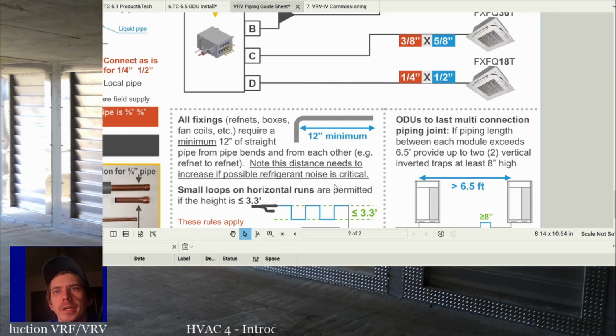So you need at least 12 inches of straight pipe, and really they tend to recommend 24 to 36 inches. 24 inches is kind of where I always try to be minimum. I never follow the 12-inch rule. I always follow 24 inches. How long has it got to be from here? 24 inches of straight pipe between any change of direction or anything like that. You're looking for at least 24.